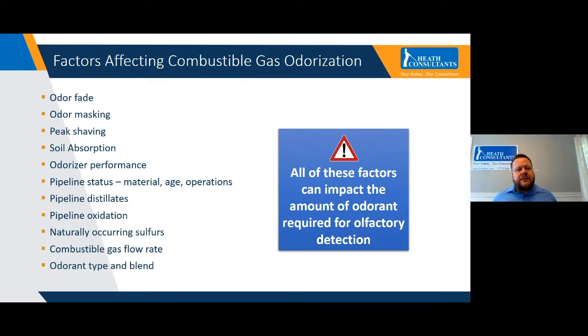There's a principle called odor masking, where if you mix multiple odorants or mercaptans together, one may mask the other. Instead of actually combining the smell, one can override the other, reducing or masking the smell of the odorant. The odorant can also absorb into the soil or into plastic pipe, reducing its ability to be detected. So there are a lot of different environmental factors that need to be taken into consideration when you're odorizing your system.